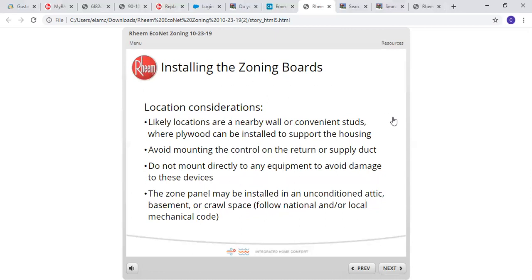When you're installing the zone boards, for location considerations, likely locations are on a nearby wall or convenient studs, or plywood can be installed to support the housing. Do avoid mounting the control on the return or supply duct. Do not mount directly to any equipment, to avoid damage to these devices and or the board. The zone panel may be installed in an unconditioned attic, basement, or crawl space. Follow national and local mechanical codes.